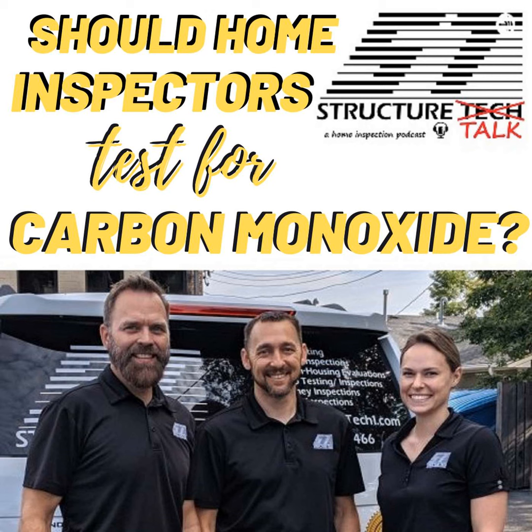But one trick for you, if you are going to drill that hole, my advice would be drill the hole down in the flue at a 45-degree angle, so that if anything ever does come loose, condensate is going to drip back into the flue and not leak out. There's your little tip of the day.